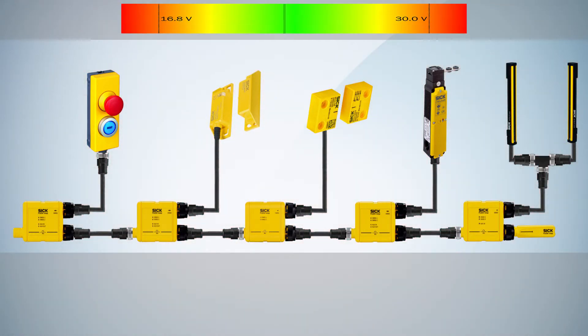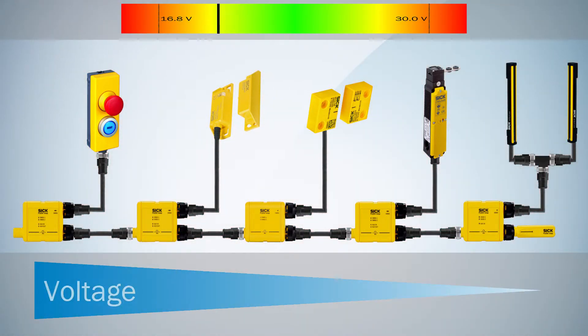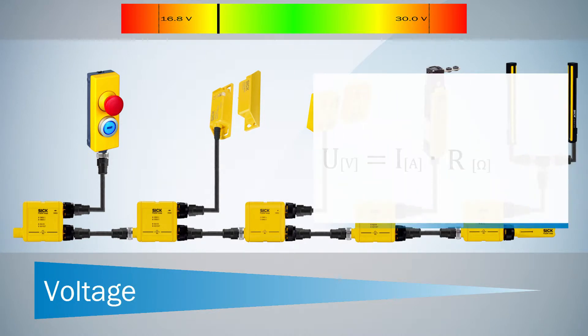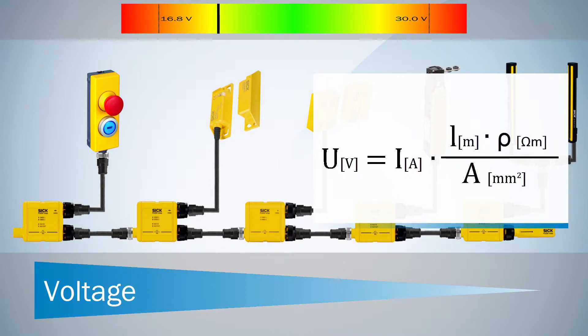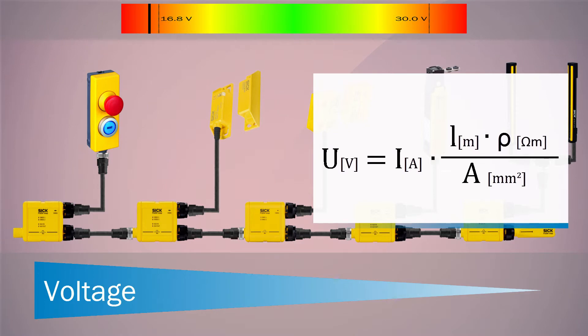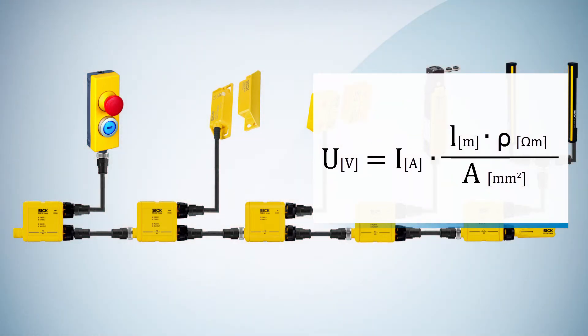On the other side, the voltage decreases along the cascade due to the voltage drop over the cables. The voltage drop is defined by the current and the cable resistance, which depends on the wire diameter, the cable length and the temperature. These circumstances may lead to the fact that nodes are not sufficiently supplied with the necessary minimum voltage. To reduce the voltage drop, you could for example increase the wire diameter or reduce the cable length, so that the resistance is decreased.